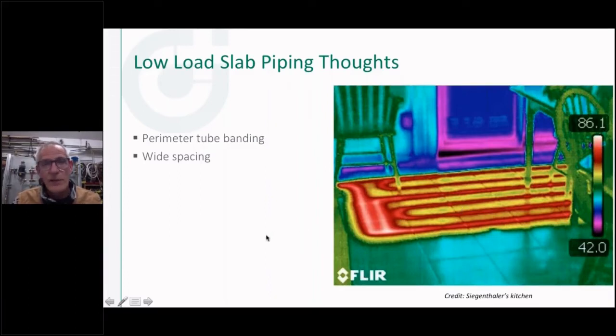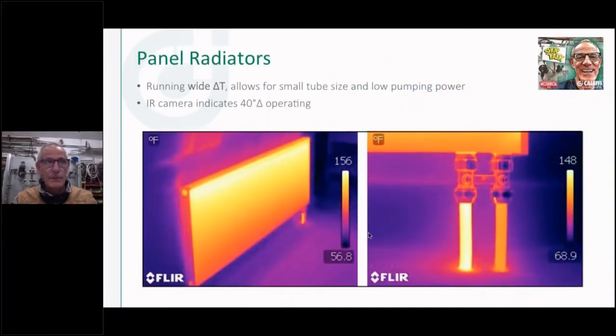You could maybe put some panel radiators in there also, which would be another way to cover a low load condition. But just know that if I cover this entire room with radiant tube, it's probably going to be running at 70 degrees, and it's not going to feel like a warm radiant floor to the owner of that building. Same thing with panel radiators.